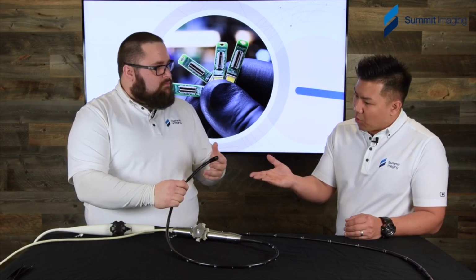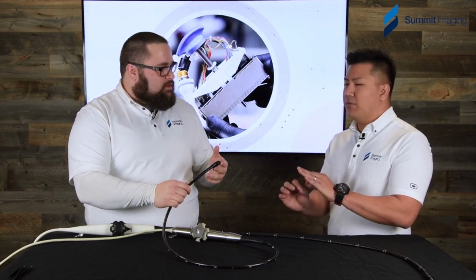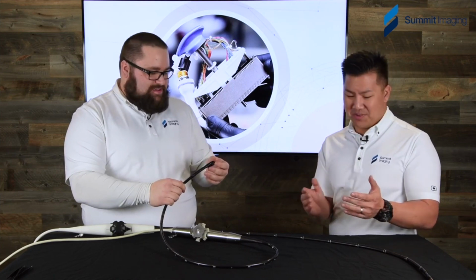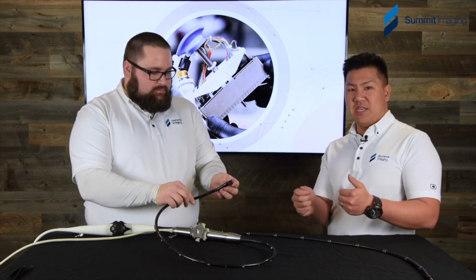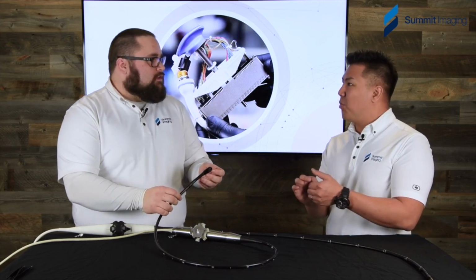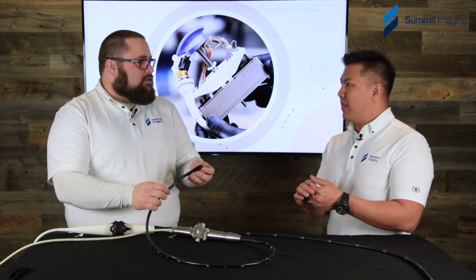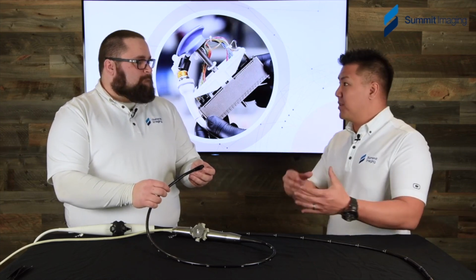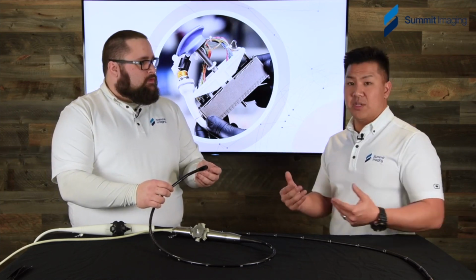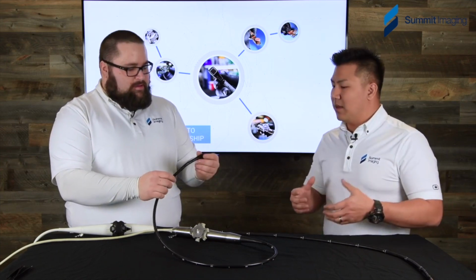Is the seal in place? Is there chips on it? Simple things like this can actually keep going on and on for a couple weeks. Yeah, and I think those are really important because if there's a small chip, even using a magnifying glass, you actually bring a magnifying glass to your classes. What may seem nominal, it doesn't take much more than a pinhole for fluid during a sterilization process to seep through. And the other opportunities when the probe's inside the esophagus and there is a small pinhole, because the muscles in our body will actually start pushing in the stomach acid into the electronics on the inside.